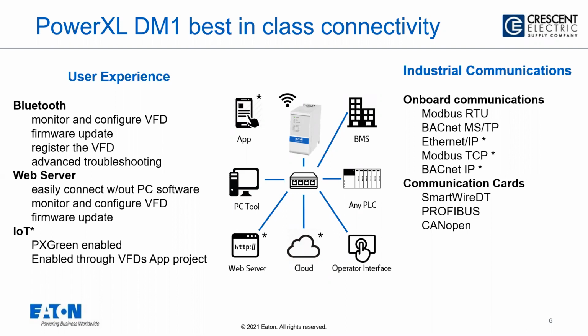And then if you need to move up into going into, for example, Ethernet IP or some of the Ethernet protocols, the DM1 Pro will get you there. The communication cards, so we do have a communication protocol called SmartWire DT, and what's nice about that is it's a way to simplify the network. It actually is an open protocol, but Eaton supports most of the products on it. It allows us to connect things like our PLCs, our push buttons, lights, and a number of other types of devices, including drives, onto this very quick, really wire-reducing network. So it allows you to link a lot of things together without having to use discrete I/O and analog I/O. And we also carry as an option Profibus DP, and then we also have CANopen on it. So a lot of really great features from a connectivity standpoint.